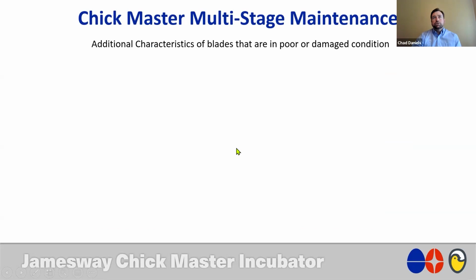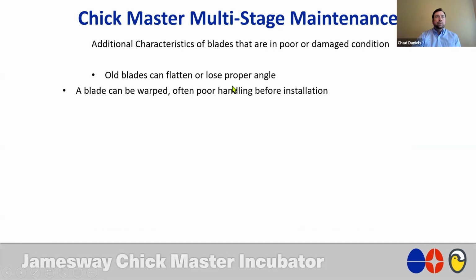So additional characteristics of blades that are in poor, damaged condition: you see old blades a lot of times that are very, very old, and because they've physically operated under such a high static for so long, they'll actually try to flatten out a little bit or lose proper angle. So it's important to update those periodically.